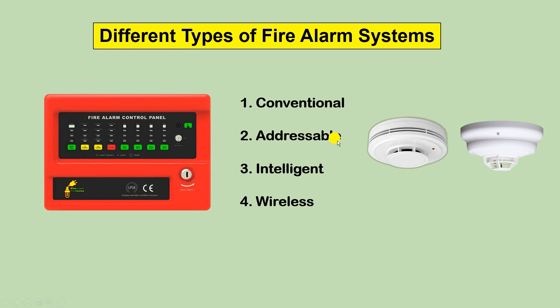The second type of fire control panel is addressable. In an addressable fire alarm system, each detector has a set address. If fire is detected through a detector, the control panel will display the number or address of that specific detector, so you can track the exact location of the fire, unlike conventional type where you only know the zone.